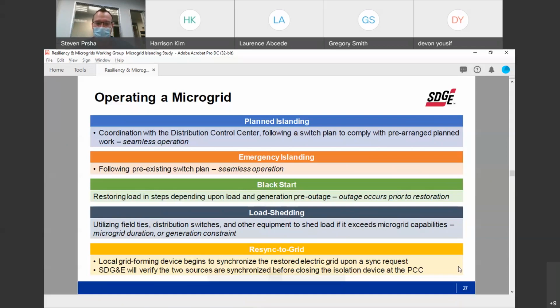Ultimately, that device begins to synchronize with the grid. Once it's synchronized, it then talks to our protection relays, and our protection relays do a second check to double confirm it truly is synchronized. Once that's performed, the breaker or recloser, whatever it happened to be, will then close.